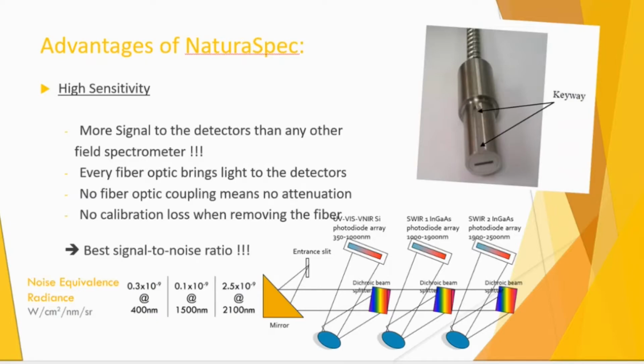In order to do that, you can see a picture in the upper right corner here where the fibers are terminating into a slit, and that slit matches perfectly with the entrance slit to the instrument. So instead of having just a round circular bundle of fibers, we are directing every single fiber to that slit. So we are ensuring that there is no loss of signal through that fiber. Another advantage is that we are not using any coupling between fibers here, so there is no attenuation because of couplings. Every time you have a fiber optic attached to another one, there is a loss of signal. Here we don't have that, because again we have the direct mating of the fiber to the spectrometer.